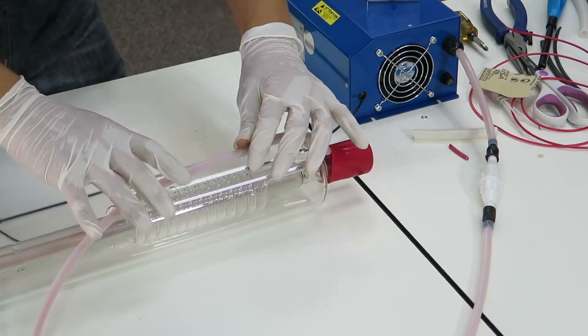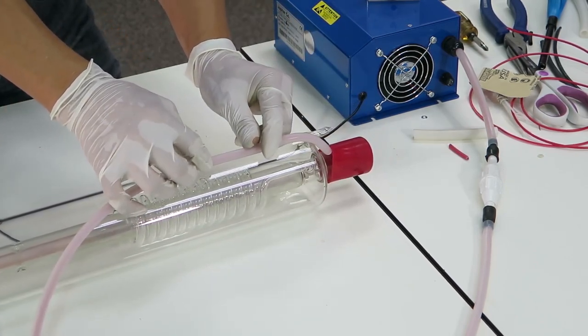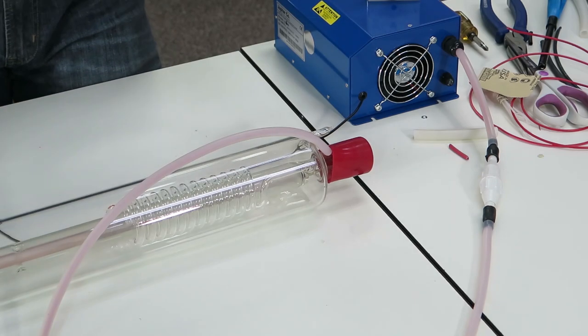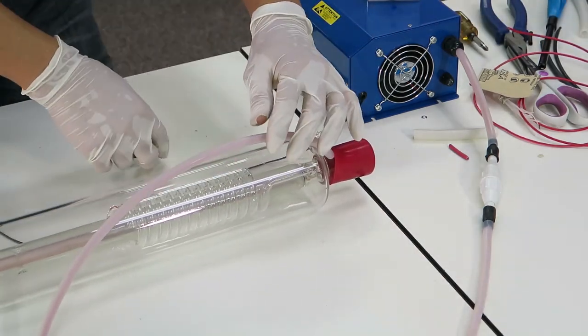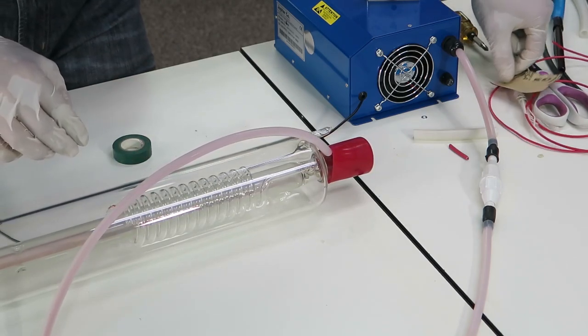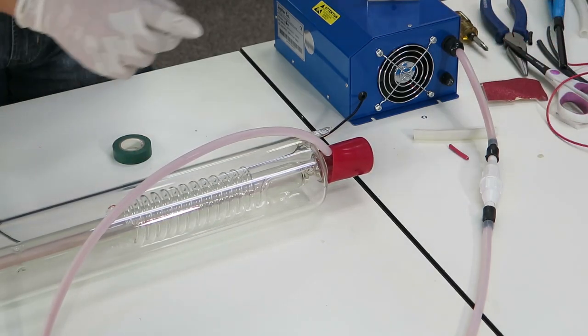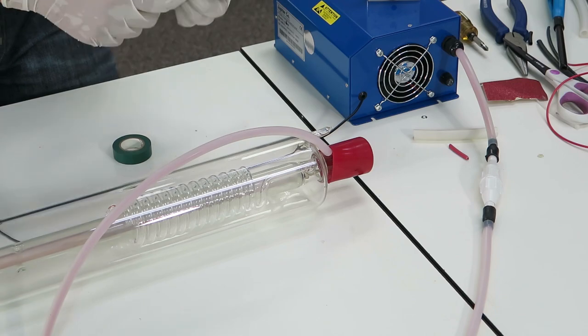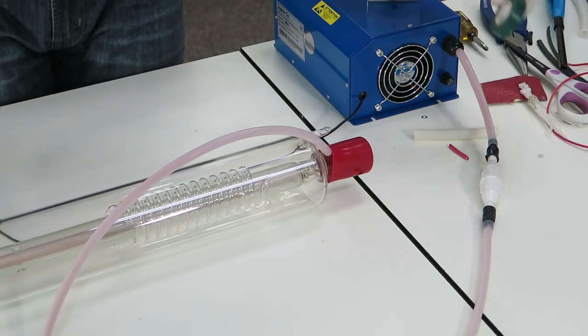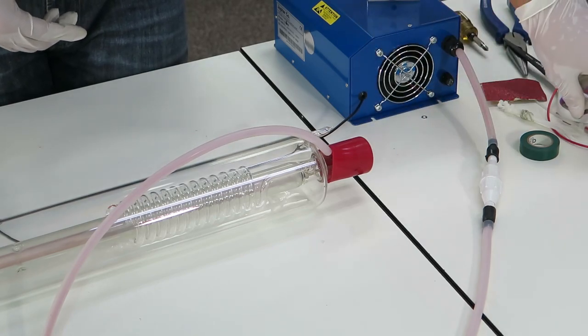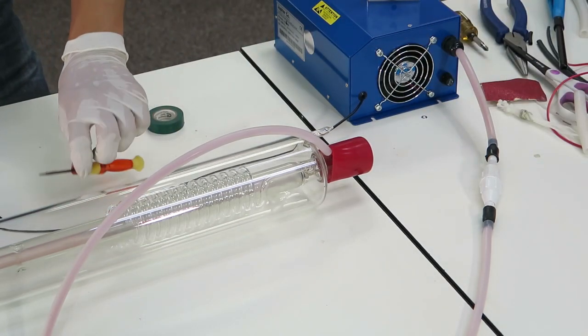I remember when I repair one of the machines, and I did a test because the customer didn't have the cap on that tube. It happened that the arcing, the length of the arcing is almost two inches. So, the arcing is jumping from the high side to the chassis, and it reset the controller all the time. All right. So, remember to put the caps on. And you want to secure the wire, either use an electrical tape to wrap it up, or use longer cable tie to wrap it. But, so I'm not going to do it right now. I'll let you guys do it.